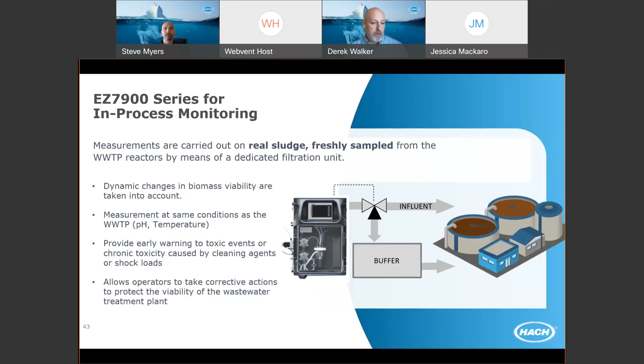I'll show you over the next series of slides how this technology works and why it's a benefit, with a case study that has recently used this technology. So we are doing respirometry, and we are taking a measurement of respiration rate by use of a dissolved oxygen probe in this instrument. Multiple influent streams can be sampled. So if you've got either a septage dump or multiple influent streams from the collection system, each one of those can be sampled individually and brought into the instrument on a cyclical basis. You can actually monitor multiple influent streams at the same time.